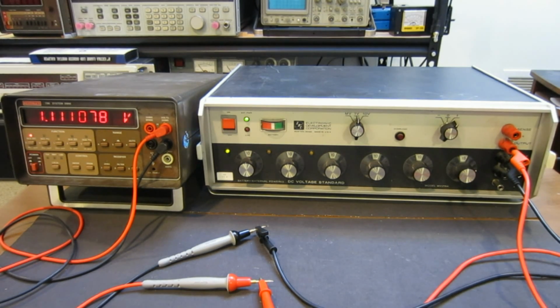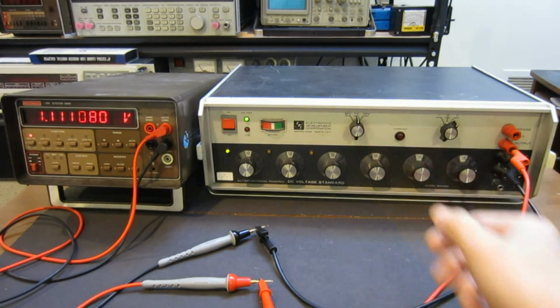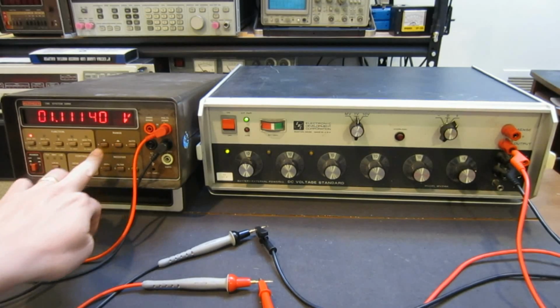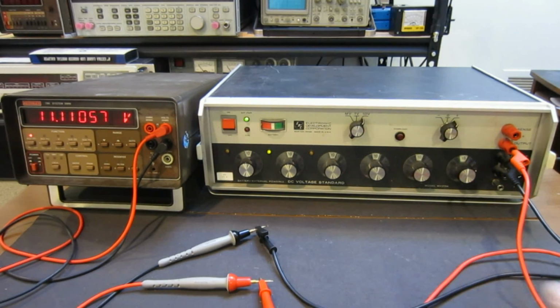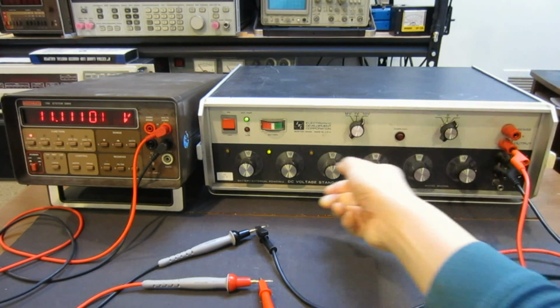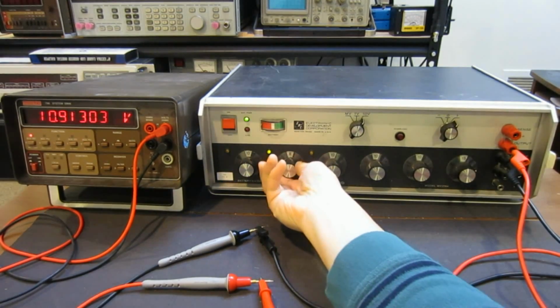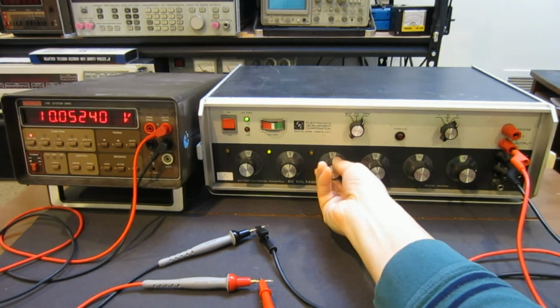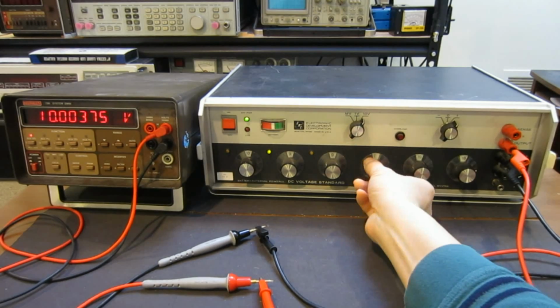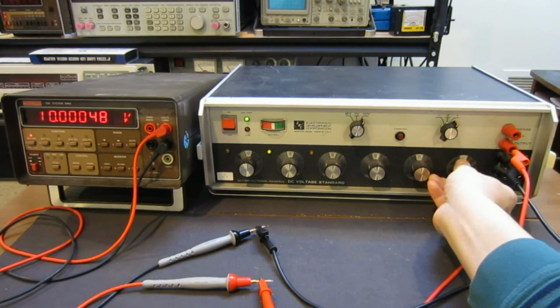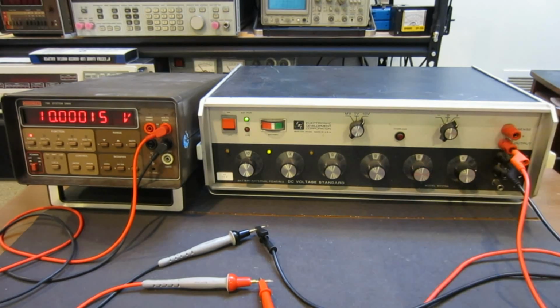Let's take a look at another range here. Let's move it to the 10 volts. Before that, let me change my setting here. So the 10 volts, again, no problem at all. 11 point. Let me just turn this back down, and hopefully it will show very close to 10.000. As you can see, it indeed shows 10.000, and the last few digits do oscillate a little bit, but that's to be expected as we are down to the limitation of both of the instruments, actually, in this case.